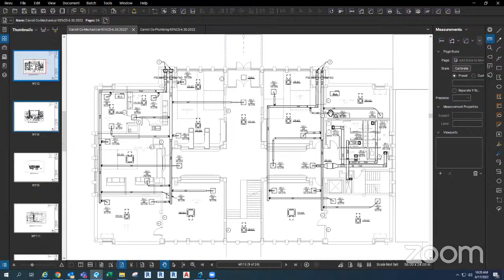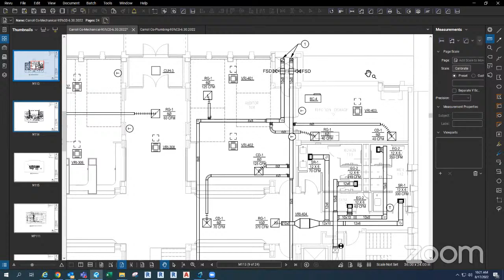With this VRF system, you'll see these boxes around here called branch controllers, though that name varies by manufacturer. Refrigerant piping from your outdoor unit mains will come to these branch controllers, which have up to 16 different taps serving your indoor units. The branch controller is like the brains of the system, taking refrigerant from the outdoor unit and distributing it to simultaneously heat and cool the spaces.